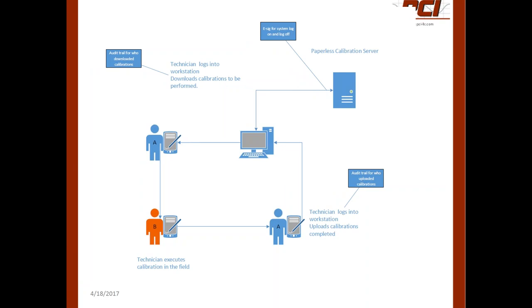In a two-person calibration, individual A logs into the solution and downloads the calibrations they're expected to execute. So from a system perspective, the audit trail says technician A downloaded and executed the calibrations. But technician B is the one actually holding the handheld and entering the data, because technician A is up on a ladder somewhere in an obscure location, yelling down to technician B what the data values are from the calibration.